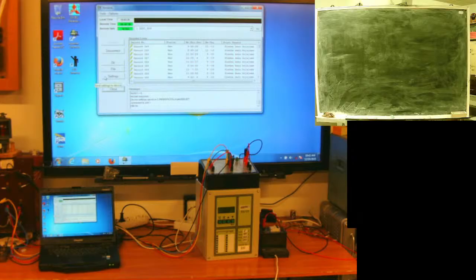Now, the mainstream approach is to use a time signal from the global positioning system - an IRIG-B signal. It's very precise, appears very reliable. It's reliable until the moment someone brings a military GPS jammer into the vicinity of your substation. Then trouble starts, because civilian jammers only block the navigation signal, but military ones send a fake IRIG signal. Your clocks will show anything from one time zone to a completely different one. Okay, we live in bad times.